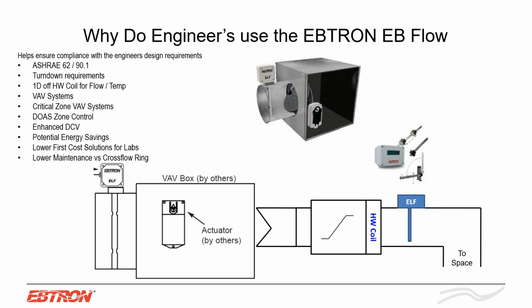Something else to think about, if you're doing VAVs with a hot water reheat coil, normally you want these installed upstream of your VAV box. But if you have a hot water reheat coil, install this downstream of the coil. The coil acts as a flow straightener. Install it 1 duct diameter downstream. Now you're getting your flow, you're getting your leaving air discharge temperature all back to 1 unit. So as an ATC contractor, this is cost savings instead of installing a separate temperature sensor.